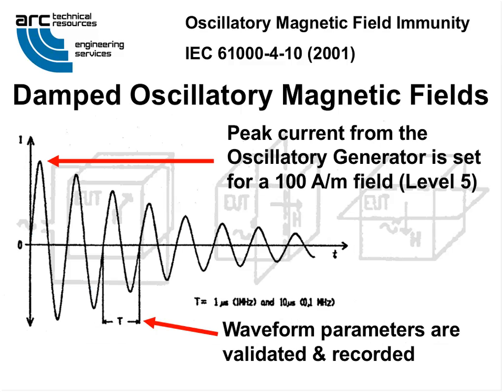The peak current from the oscillatory generator is set to a validation current that you can measure. Typically it's 1/10 of what you're trying to deliver. So that first peak is critical. And the parameters, mostly the period, or T as it's shown here, either 1 megahertz or 100 kilohertz, are the 2 critical waveform validations that are required to be included in the test report.